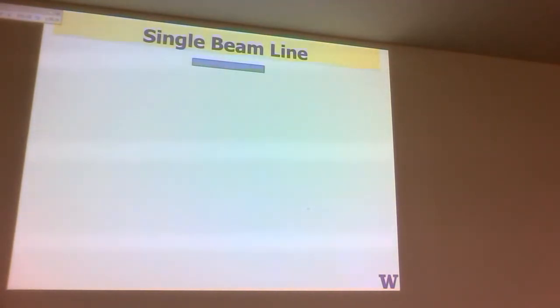So we call that fixed focus transmit, dynamic focus receive. And just like you said, I have one lens on transmit and I have an array of lenses on receive. All right? And what the modern scanners are doing is, you don't fire with the whole array anymore. You fire with segments of the array that are coded in a way that you can get some information back and retrospectively put back together multiple lenses on transmit. That's the new way to do it. You have all these elements.